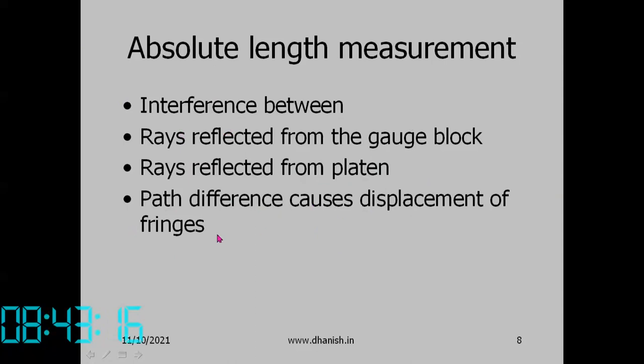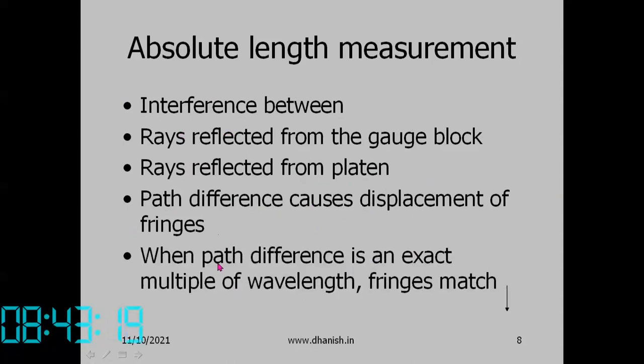How can we measure absolute length using this interferometer? The interference between rays reflected from the gauge block and rays reflected from the platen — path difference causes displacement of fringes. When the path difference is an exact multiple of wavelengths, the fringes will be matched; for other path differences, the fringes will be shifted.